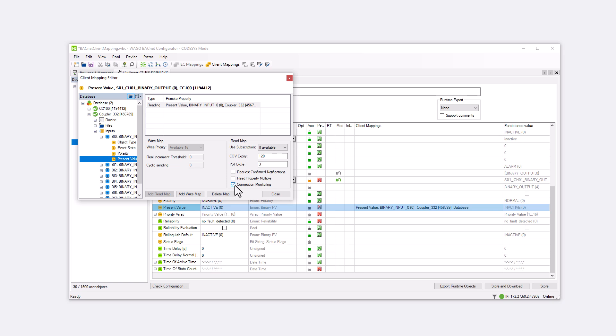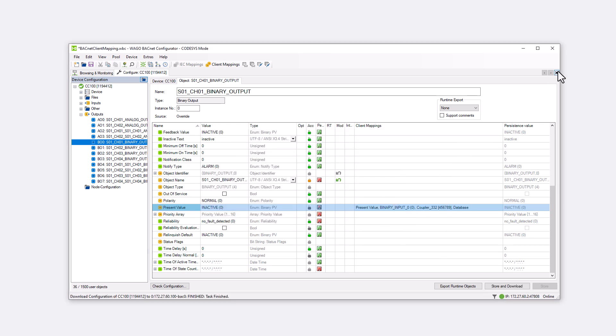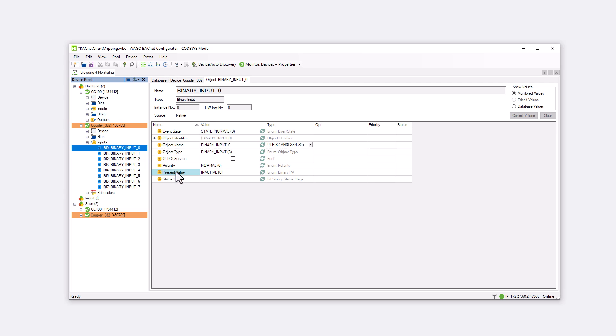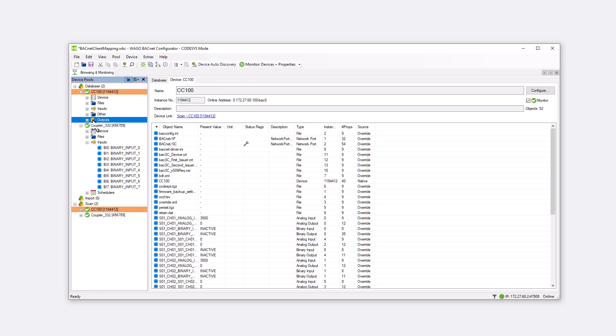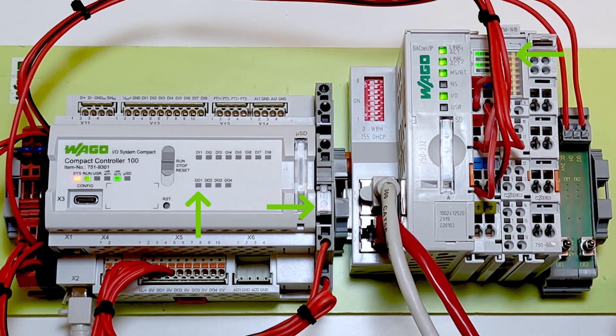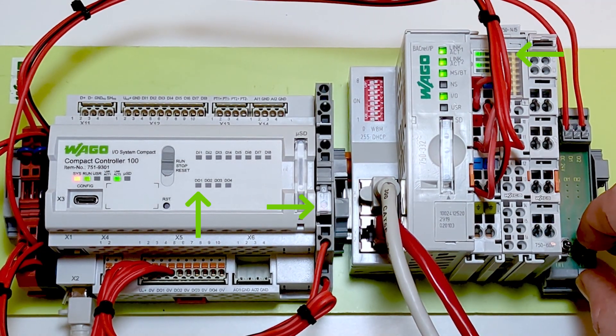To test the Read function, we need to close the Editor window. With store and download, we save the settings and upload them to the controller. In the input properties of the first digital input on the coupler, we can see how the present value switches to true as soon as we apply 24V to the input. Switching to the digital output on the CC100, we see how it also reflects the true or false state.